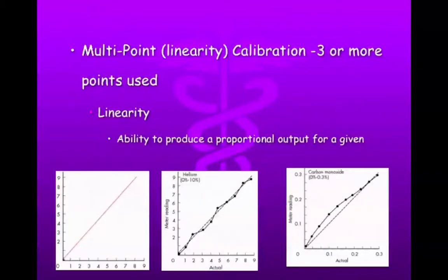Okay, so we talk about calibration. We can also look at analyzers and anything that analyzes a gas. So if you have a blood gas machine, it's going to analyze PO2 and CO2. Those are gases. So you've got to have some mechanism to produce samples that would be a certain way based on certain conditions when tested. The same thing can be said for helium dilution. You've got to analyze the helium. You're not going to know what you're starting with unless you analyze it, or how much oxygen you're starting with unless you analyze it. We actually do calibrations. Blood gas machines are a prime example of that, as are some of your PFT machines.